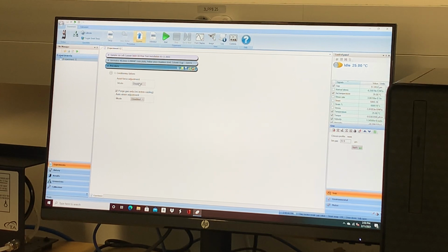What it does is control the axial force. You may just say keep the axial force at 0, or you can put some force on it. Once the sample starts to expand or contract, the instrument says, oh, I need to keep this at 0, so it'll move the gap up and down to do that. So only for samples that expand or contract. Or if you were doing torsion, a different type of geometry, you would maybe put some tension on a sample. Then sample loading would be temperature stuff, or target gaps, or closure profile. And then you have end of the test stuff, like once the test is over, set the temperature back to where you want it to go.